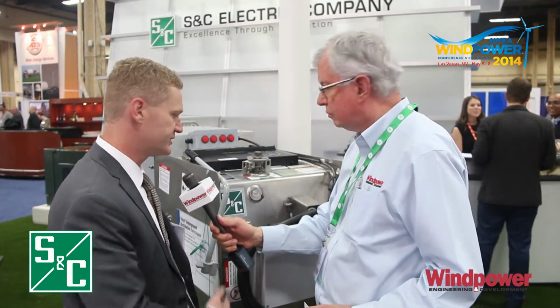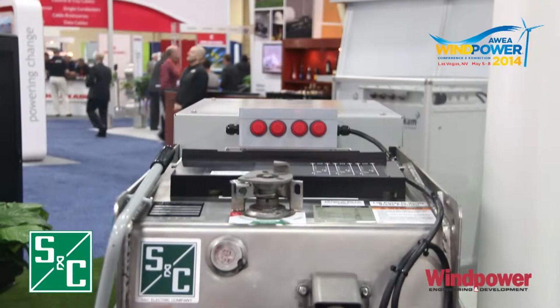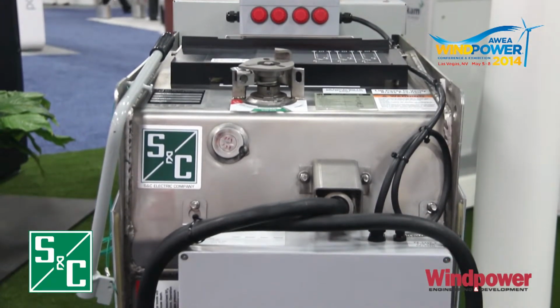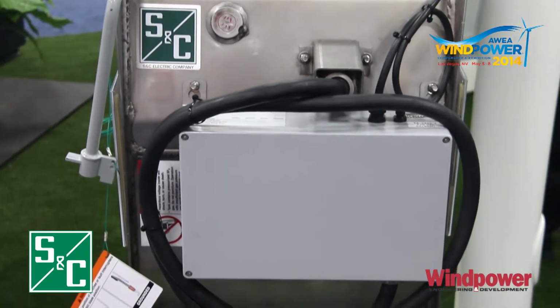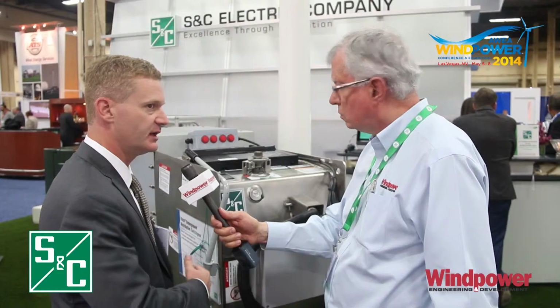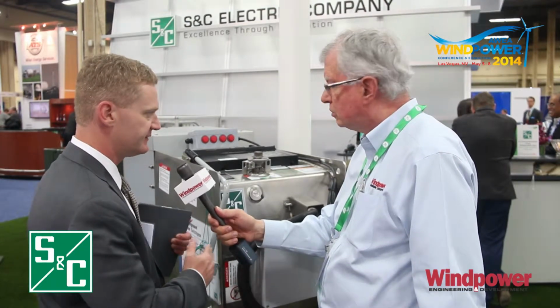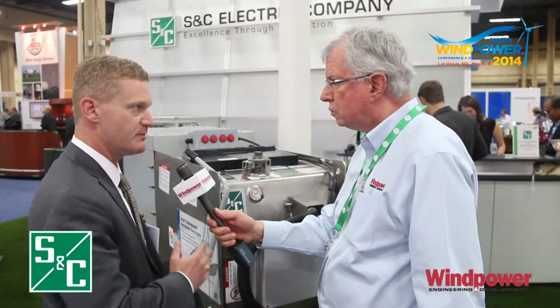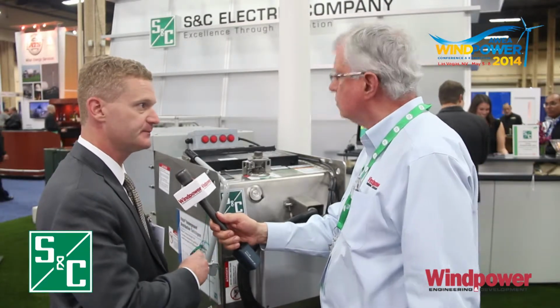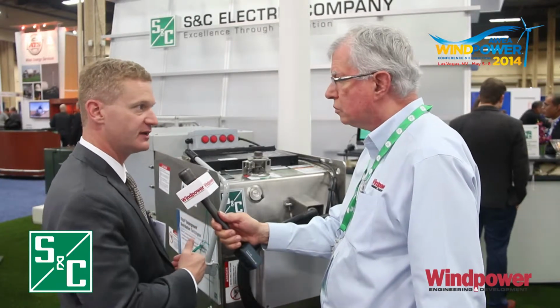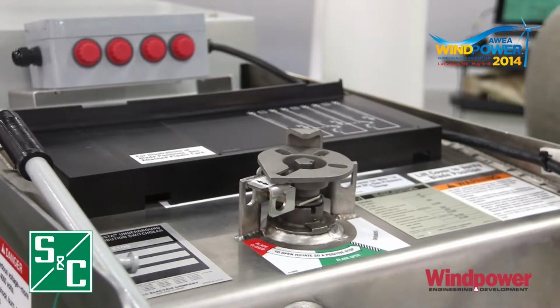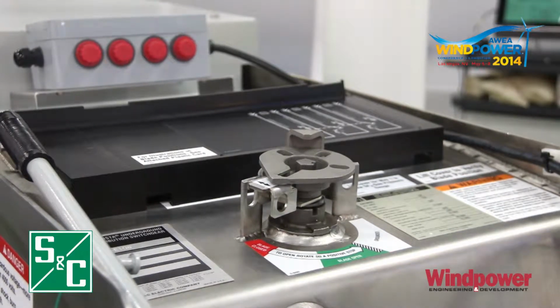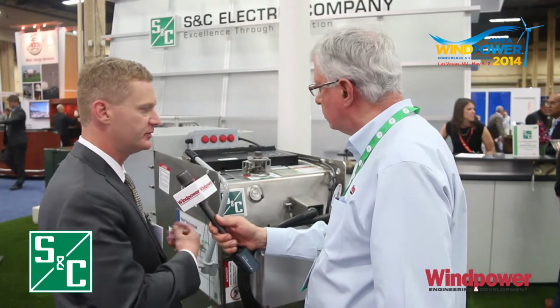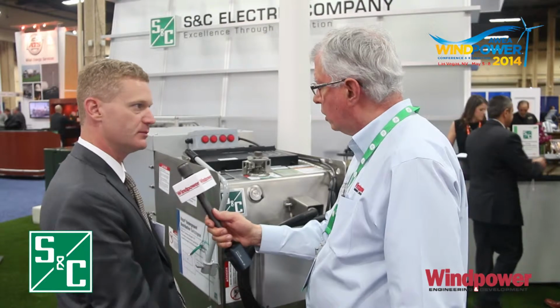Well, this is our Wind-Turbine Vista Switch, an SF6 gas-insulated disconnect switch. It goes into the base of a turbine, part of our typical Vista lineup of switchgear, a very common lineup for us. This one was developed specifically with wind turbines in mind, designed to go in the base of a wind turbine that comes down tower at 35 kV, 34.5 kV. It was designed to actually go in and out of the door of the wind turbine, so if it needs to come out for maintenance, or if they're moving it around, it can come out of the door and then go back in.